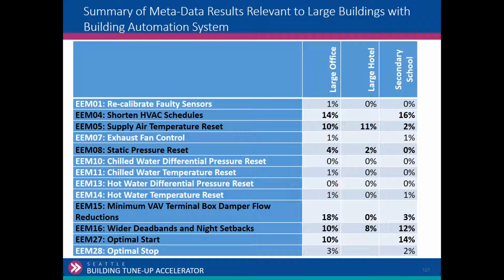And there's a variety of reasons for that. It may have been a change in occupancy, or if it was a squeeze box, maybe it was dumping from the box, so they increased the minimum air position. There were a lot of reasons, but that was an opportunity they saw in a lot of cases, where maybe it was set at 30%, 35% because it was a conference room initially designed 10 years ago. Now it's being used as an office and could be set at 10% minimum flow. So this was an area they saw as a big area of potential savings. Did the minimum VAV damper position make sense?